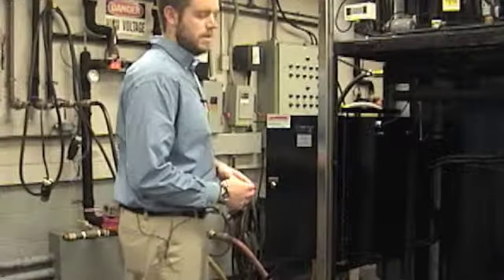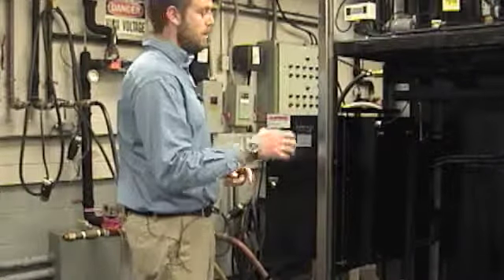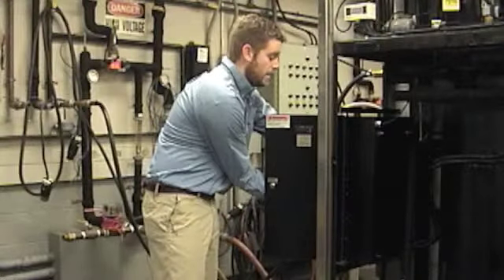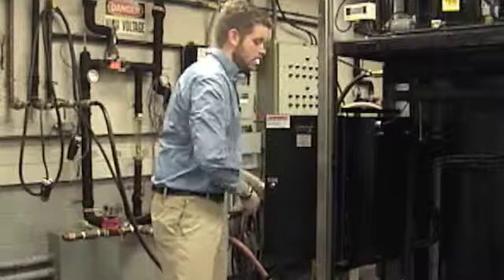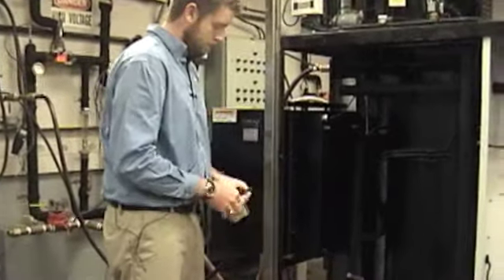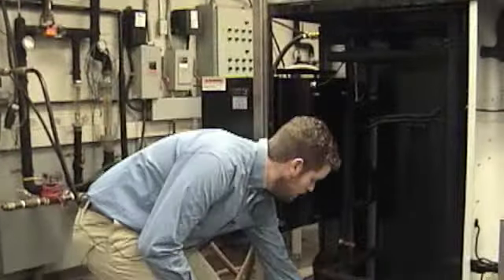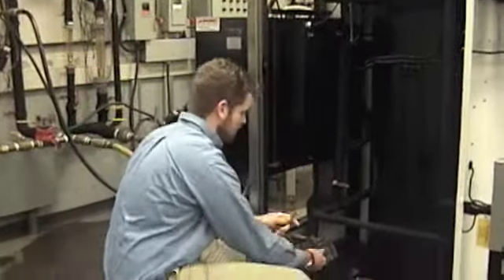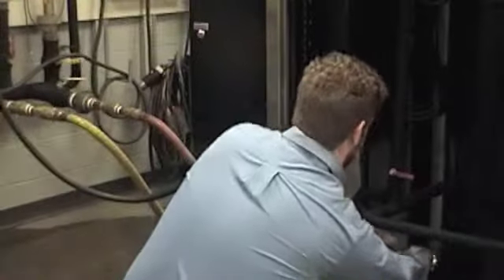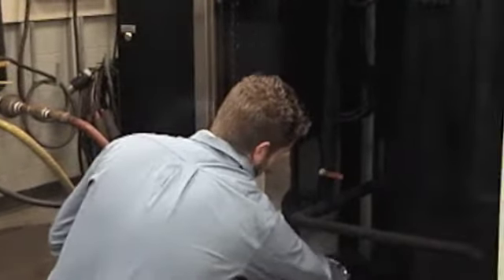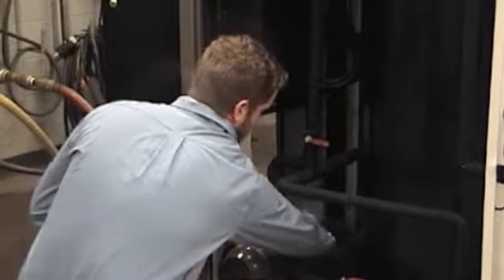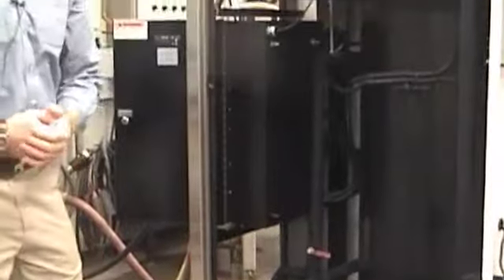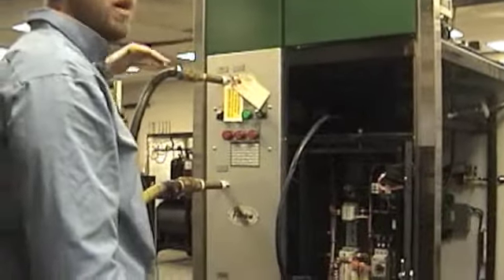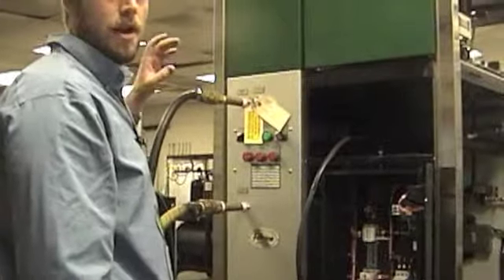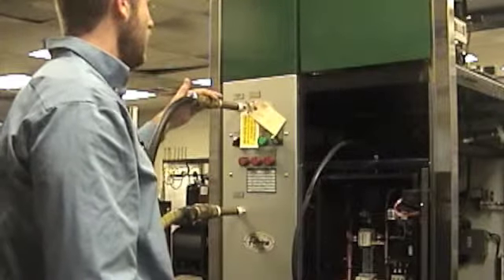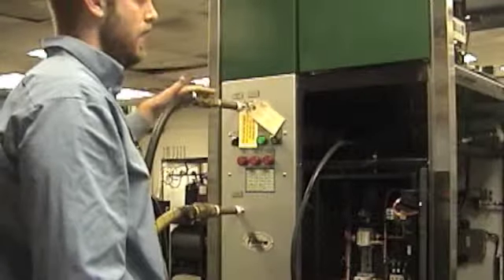The sterilizer has been assembled, the filters and purifier cartridges are in. Next, we'd want to put the pump plug in the pump so we can begin filling the unit. Pump plug's right in here in the electrical box. You're going to want to remove it. Using a ratchet wrench, you'll put the pump plug into the unit. You want to make sure you do that so that when you fill it, water doesn't come pouring out of the pump. If this was installed in the field, you'd have hard insulated piping on the water in and a ball valve here. We recommend that they're installed with a shut-off valve right outside the unit, so you can fill it and you can isolate it if need be for service.